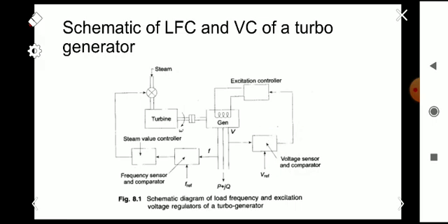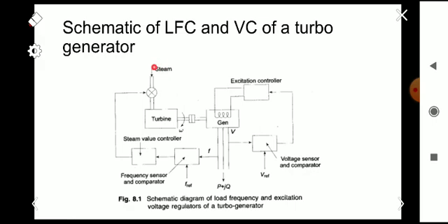The error signal from the voltage comparison is used to control the excitation of the machine correspondingly. The frequency is also controlled — it is sensed using a frequency sensor, compared with the reference frequency, processed, and this drives the steam valve controller which controls the steam input valve to the turbine. So the frequency control and voltage control can be viewed from this schematic diagram — this is the main basics of Automatic Generation Control.